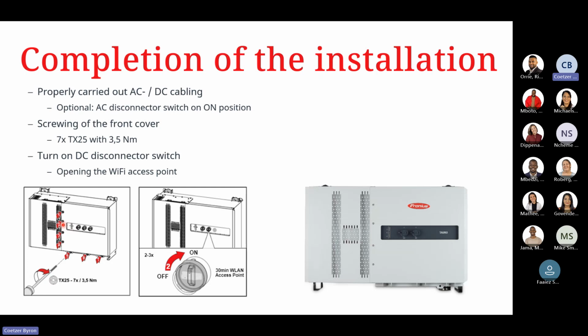So for the completion of the installation, once we have properly carried out our AC and DC cabling, we will need to make sure that, optionally, our AC disconnector is in the on position. We'll screw on the front cover with 7 Torx 25 screws with up to 3.5 Newton meters. We will then turn on our DC disconnector switch, and that will allow us to open up the Wi-Fi access point on the unit itself.